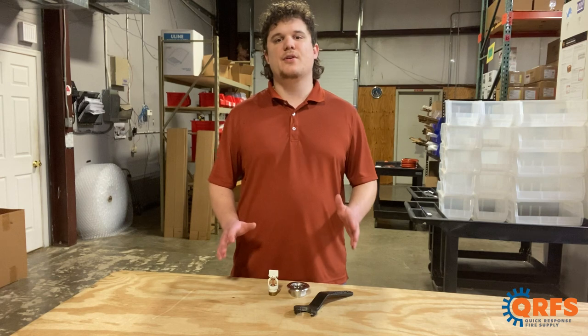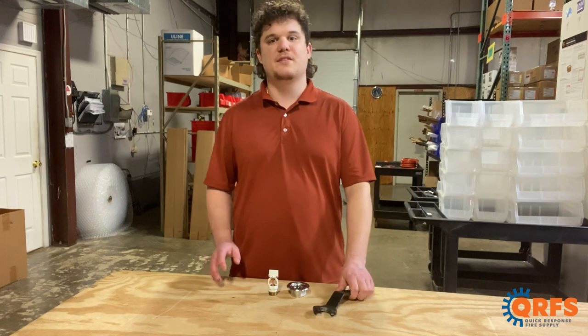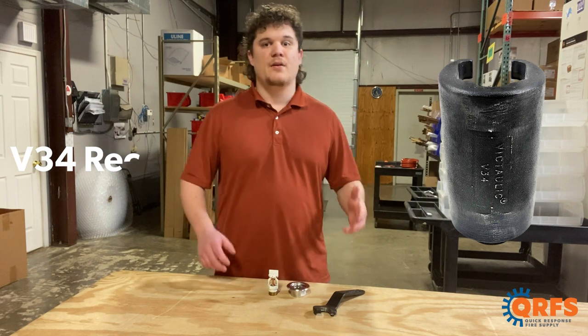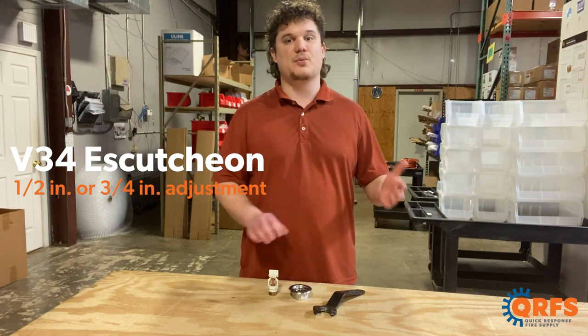To install the V3410, you will need one of Victaulic's V34 open-ended wrenches for exposed installation, or one of Victaulic's V34 recessed wrenches for recessed installation. For recessed installation, you will also need one of Victaulic's V34 escutcheons, available in ½-inch or ¾-inch adjustments.